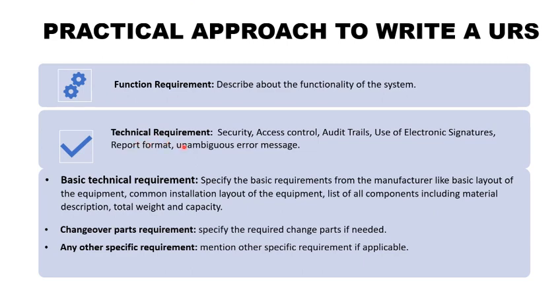Next are technical requirements such as security of system access control for different levels of users, audit trail, use of electronic signatures, report formats, and unambiguous error messages with clear instructions. Also specify basic technical requirements from the manufacturer such as basic layout of equipment, installation layout, list of all components including material description, total weight and capacity. Define consumable or changeable parts required in routine operation, and mention any other specific requirements if applicable.